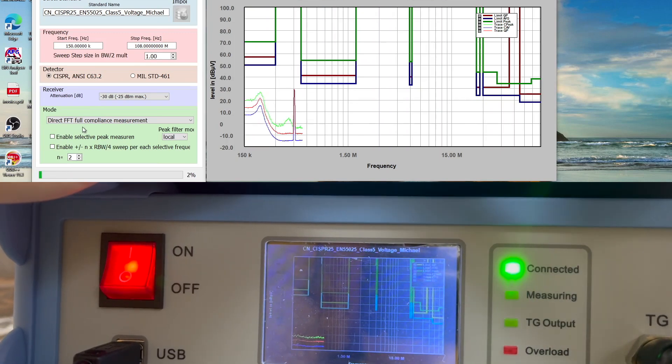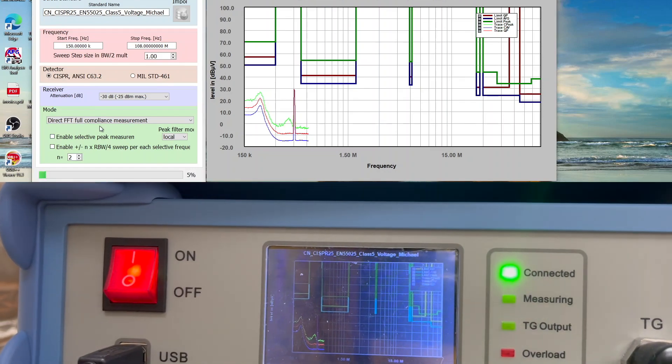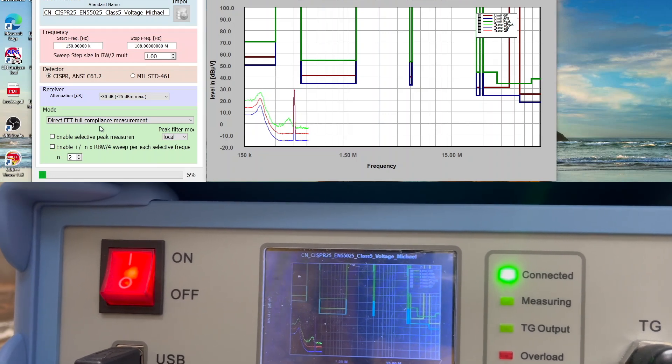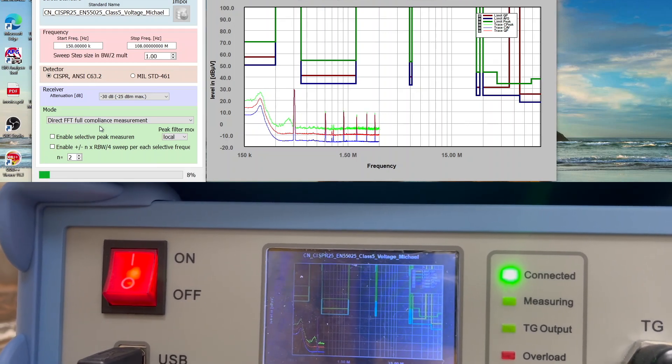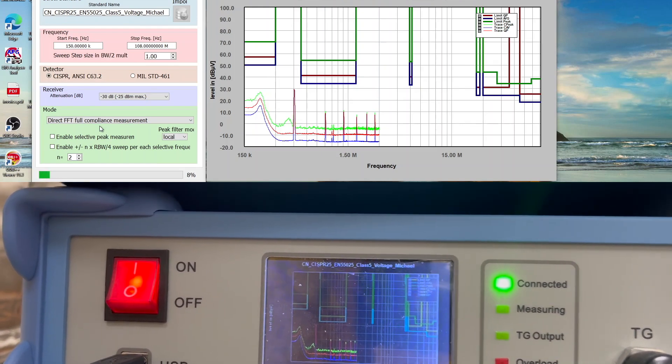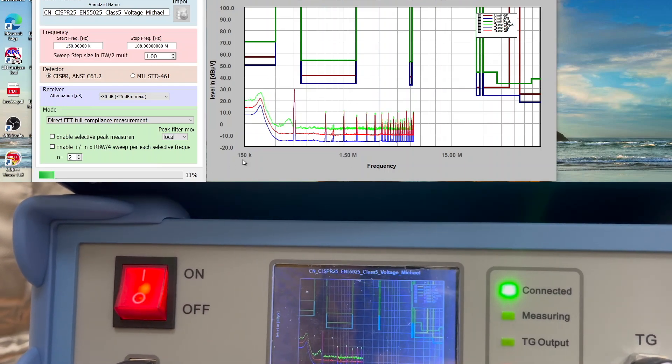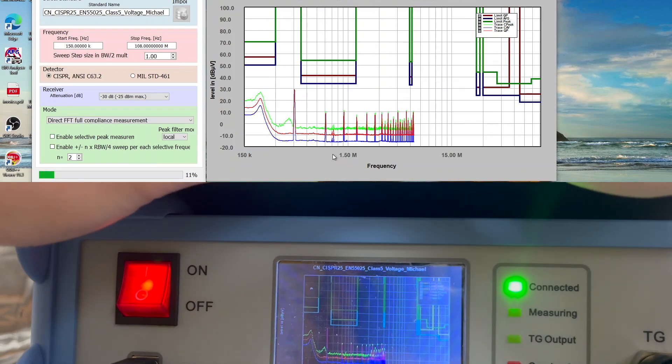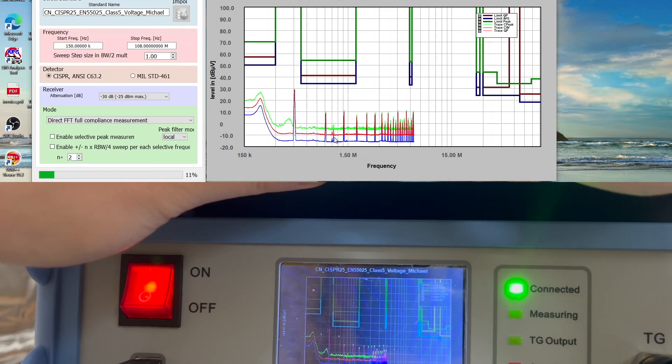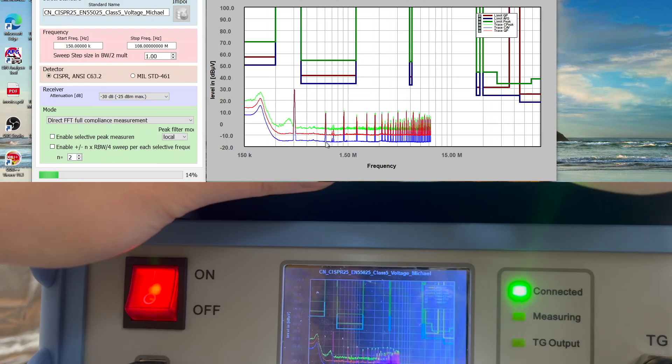Let's do the measurements using direct FFT full compliance measurements. So this gives me actually three results I believe - one is the average, one is the peak, and the other one is actually the quasi-peak. Because it uses FFT function, the sweep actually is extremely fast.